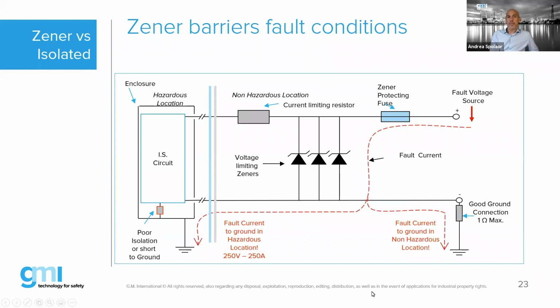In case of faulty condition, what happens with the Zener barriers? If your sensor is isolated at 500 volt, nothing happens. Your voltage will be led to the ground connection, the barrier ground connection. But if you have a poor isolation or short to ground for the field sensor, in case of voltage fault, your voltage fault will be led directly to the hazardous area. Okay, so this is possible and is very dangerous in this case.